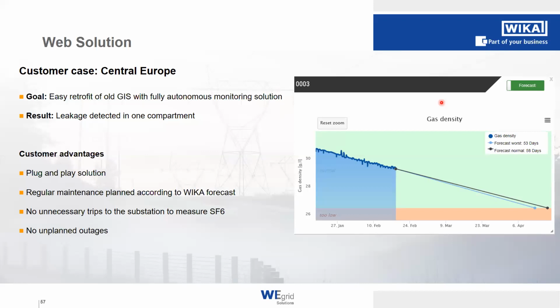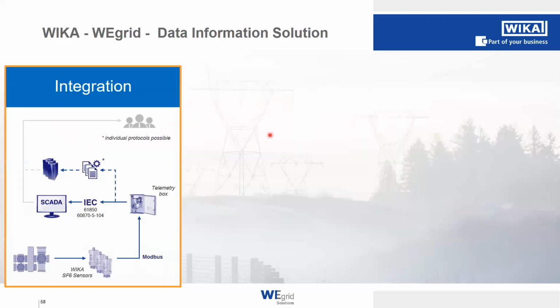And according to this, the customer was able to plan their maintenance. So that means they don't need to go to the substation every now and then to check their density. They could always check it online and see if the forecast is moving, and they only need to go there if they need to refill the compartment. That means no unplanned outages, and this complete solution was fully installed within a few hours. So it was basically a plug-and-play solution which we provided.